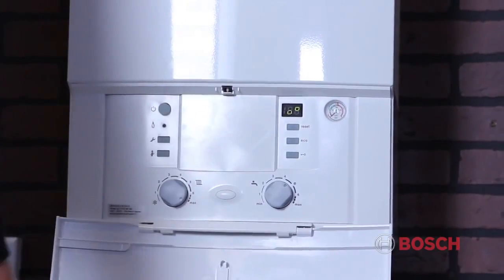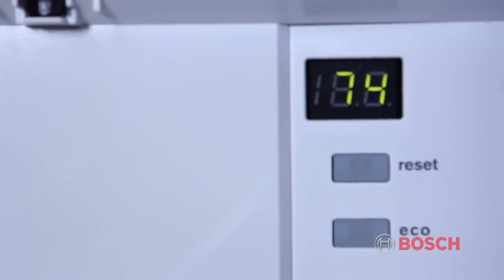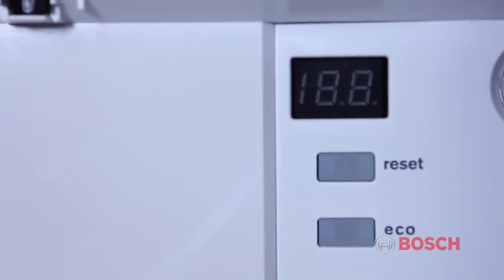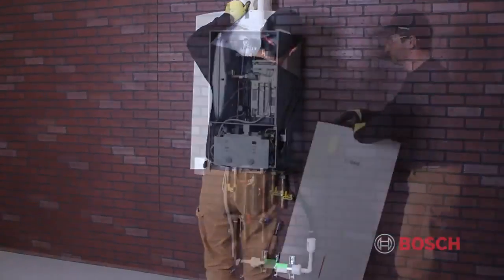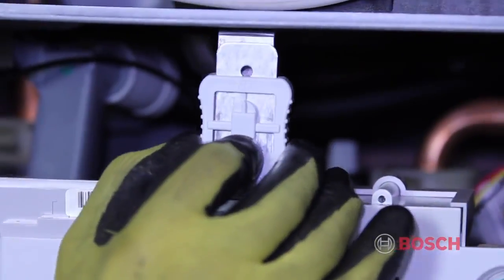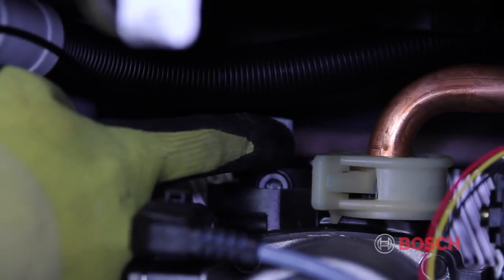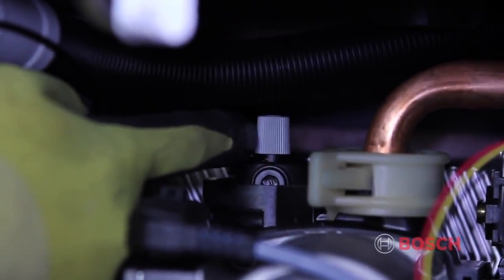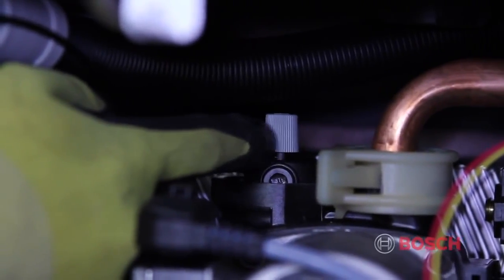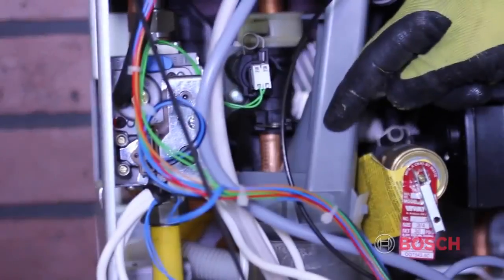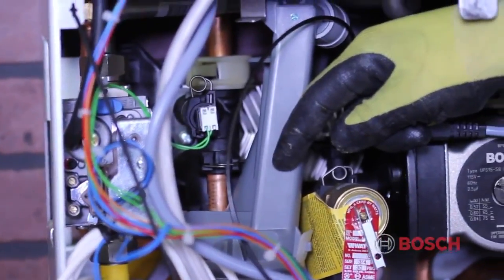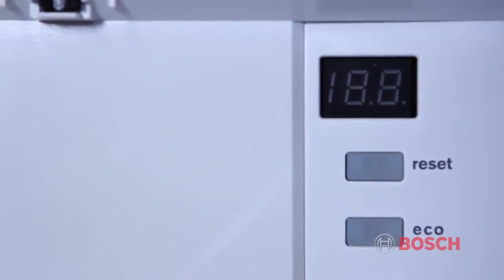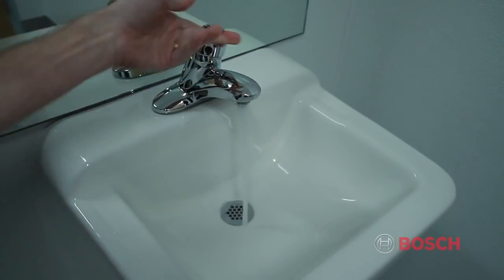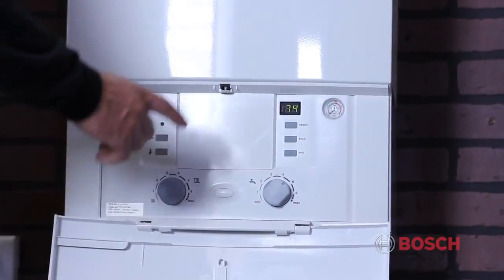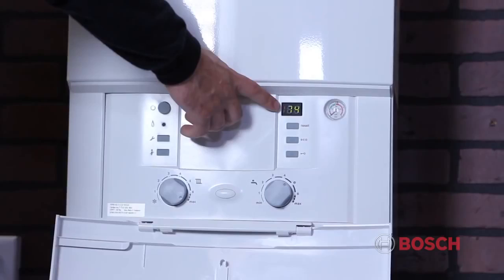During this process, the boiler's pump is pulsing, eliminating air from the system, primarily from the boiler's heat exchanger. At this time, it would be necessary to open the air vent located next to the circulator. Close it again when the purging sequence has finished. For the next 15 minutes, the boiler will run on low fire. This is done to force the boiler to condense and prime the condensate trap. This low fire sequence can be overridden in a combi boiler by turning on the domestic hot water, or for both combi and regular boilers by using the chimney sweep feature.